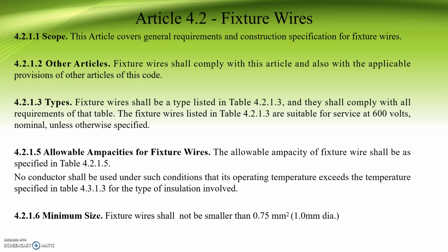So chapter 4.2.1.5, so allowable ampacities for fixture wires. So the allowable ampacity of fixture wires shall be as specified in table 4.2.1.5. So no conductor shall be used under such conditions that its operating temperature exceeds the temperature specified in table 4.3.1.3 for the type of insulation involved. So chapter 4.2.1.6, so the minimum size. So fixture wires shall not be smaller than 0.75 mm squared or 1.0 in diameter.